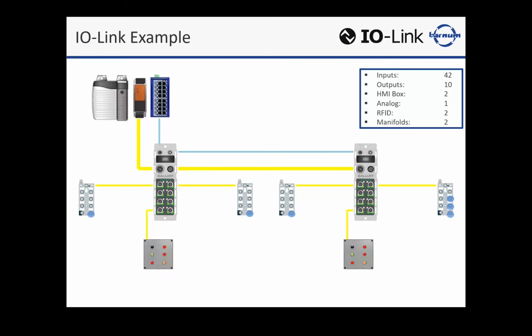So the HMI boxes are a little different. HMI boxes, this is a nice feature. If you remember in network, we had to go to a remote IO bus head, if you will, and then slice and block IO next to that. That bus head cost was $650, I think we said, John, which is a fair market price. So here what we're doing is we're actually taking an IP20 discrete IO hub, mounting it in the HMI box, and then using an M12 connector going right to a master block. So we eliminated that bus head communication device altogether, and you'll see the cost is tremendous, and you'll see that when we run the calculations. But now these are directly on the IO link network, handling the IO.